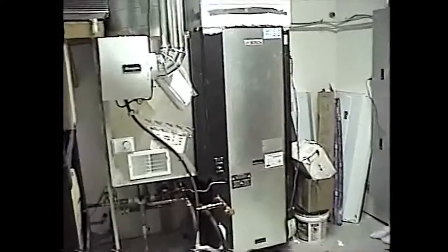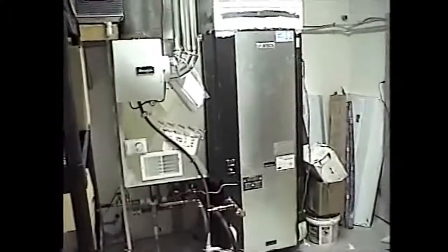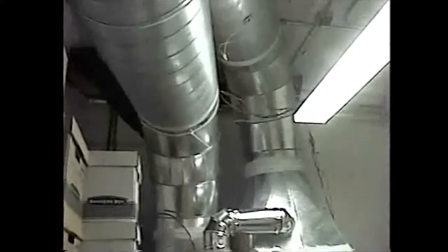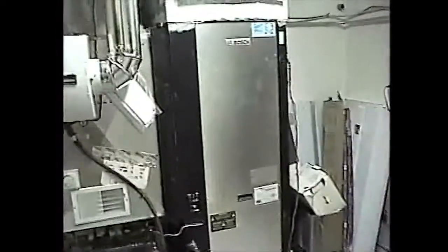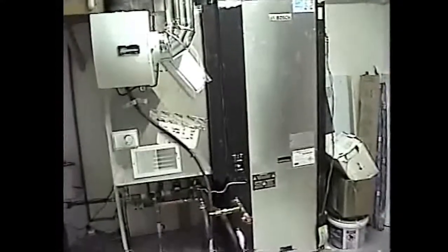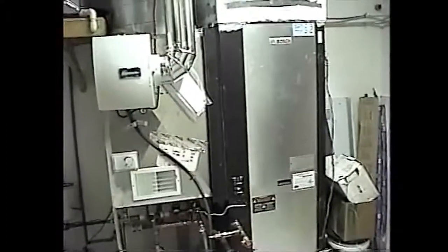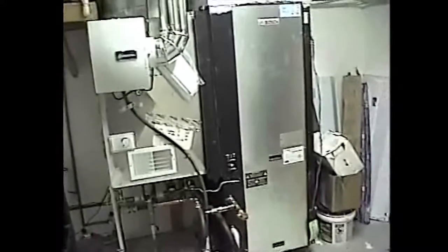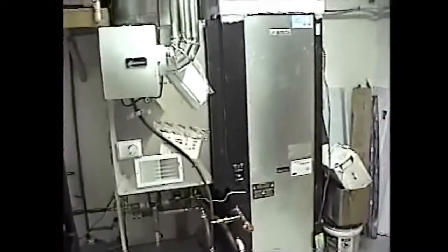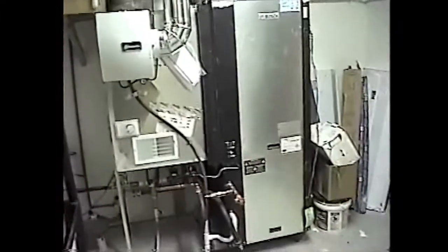What leads me to the fan handler is I laid this thing out for 3,300 CFM. Found out that the machinery, the fan coil, or the packaged unit, as I guess I would call it, the packaged Bosch heat pump, only delivers about 3,000 CFM at very low static. With the 20-inch ductwork on it, it does have a very low static. So I got a hold of Richard, and he says, well, you put my modulating control on the ECM motor and you'll see a vast improvement.